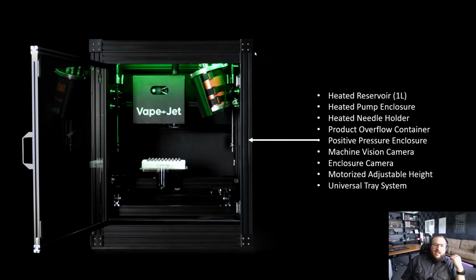The entire enclosure of the VapeJet system is positively pressured. There's an intake fan, and it's also temperature controlled. There's no active heater inside the enclosure, but we have an intake fan which pulls in filtered air, which can push out the warm air that accumulates inside from the rest of the heaters. So you're able to control the temperature inside this chamber.